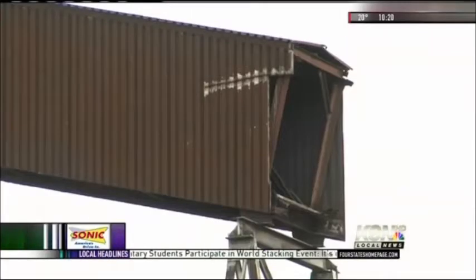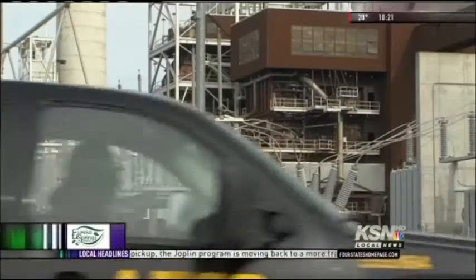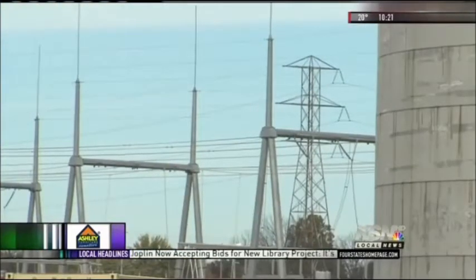Eason explains to create electricity, you need a fuel like the coal previously used at the plant or the natural gas currently used. Heat up water and you make steam, and then you do what they call superheat. When you superheat, you're actually making that steam where you can't see it — like a tea kettle, you see steam coming off, but with superheat you actually take that and heat it past that point. On that same shaft is connected a generator. The generator has a rotor and a winding of wire through it. The rotor is essentially a magnet, and as you cut that magnet through that wire, it makes electricity and then it goes out on the line for customers to use.